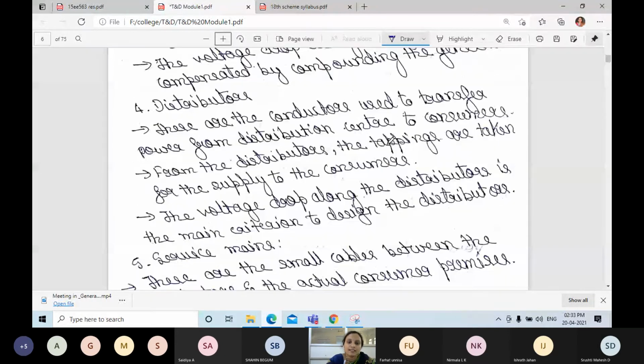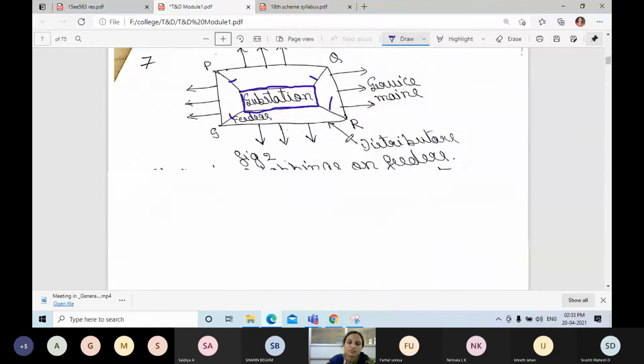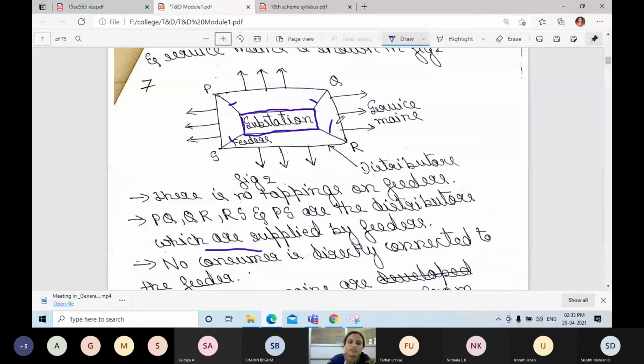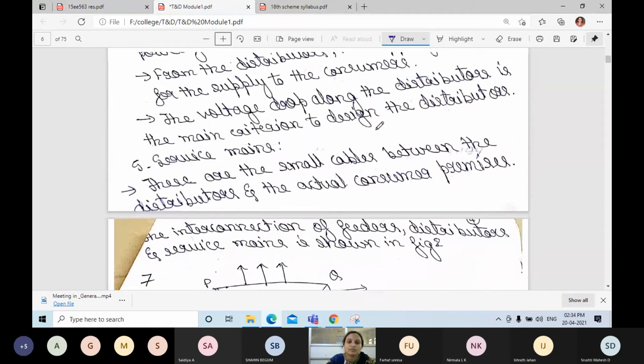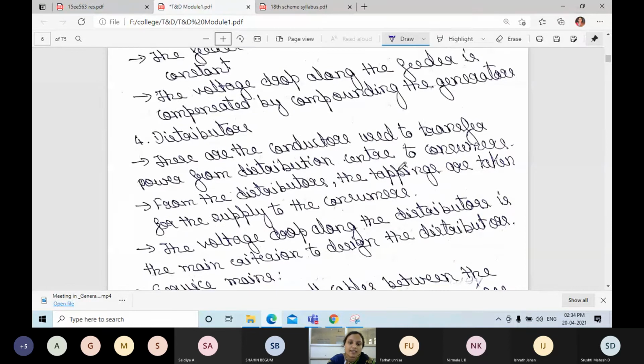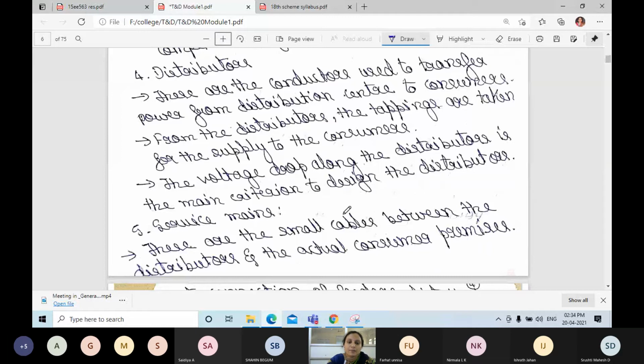Distributors are the conductors used to transfer power from the distribution center to the consumers. Okay, you understood from the diagram. The tappings are taken for the supply to the consumers. Okay, tappings means this is what the tappings are. Four we have taken from the substation. 4 tappings are available here. In distributors, the tappings are taken for the supply to the consumers. Next, the voltage drop along the distributor is the main criterion to design the distributors. How will we design the distributors? Mainly they will consider the voltage drop. Okay.